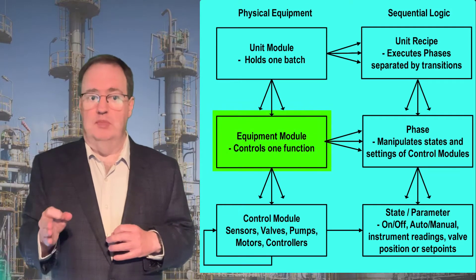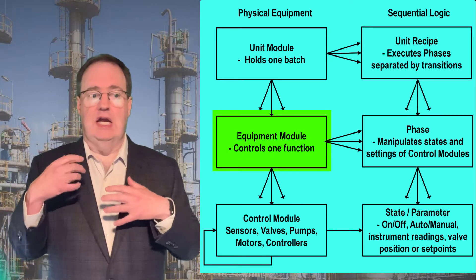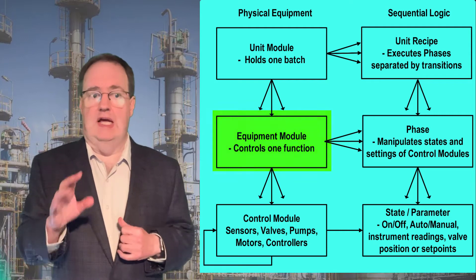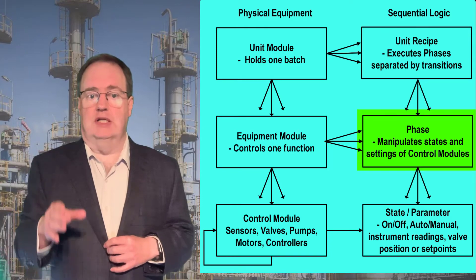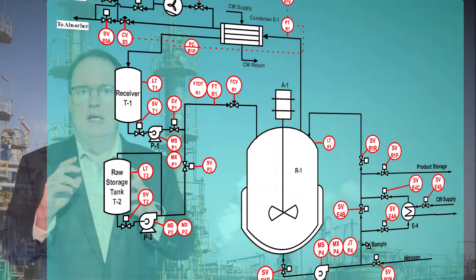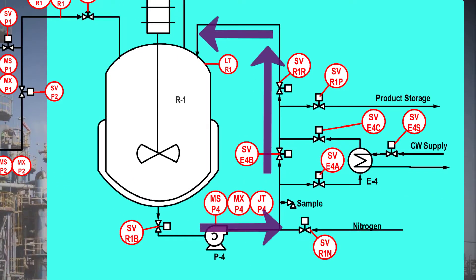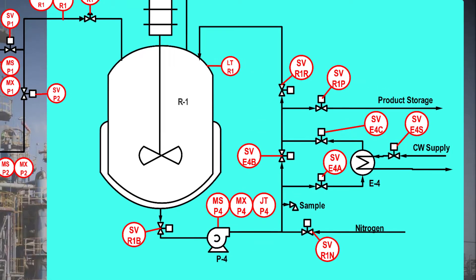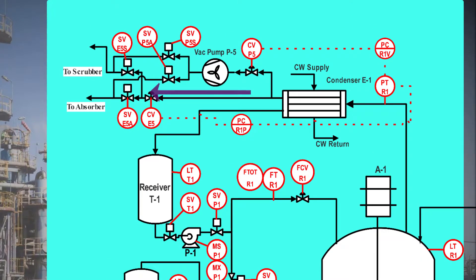A unit is made up of several equipment modules — collections of control modules or devices that can carry out a task for that unit. A phase for an equipment module is the sequential logic that accomplishes one task. For example, a reactor exit piping equipment module could have a phase for circulating and sampling the reactor and a second phase for discharging. A batch reactor could have a pressure equipment module with a phase that vents positive pressure and a second phase that pulls vacuum with a vacuum pump.